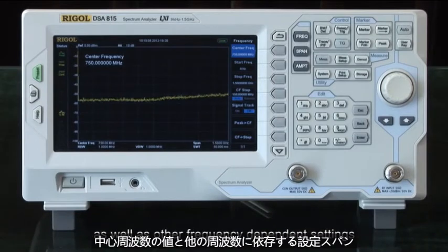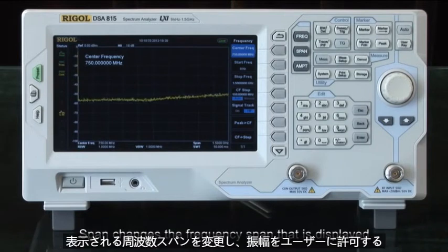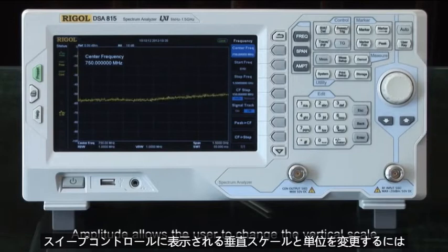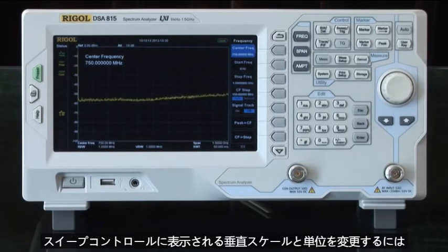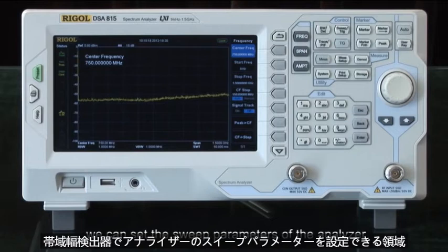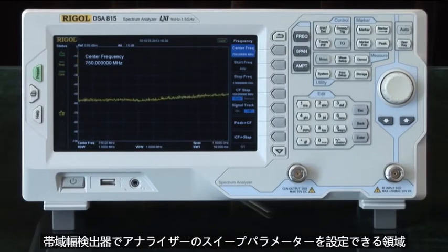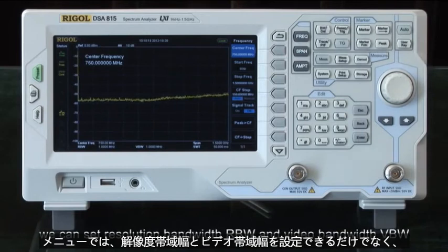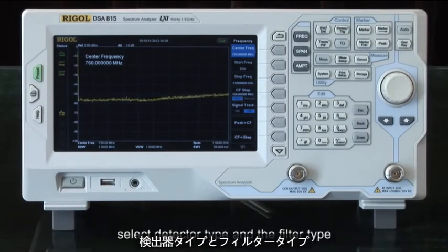Span changes the frequency span that is displayed, and amplitude allows the user to change the vertical scale and units being displayed. In the sweep control area we can set the sweep parameters of the analyzer. In the bandwidth detector menu we can set resolution bandwidth, video bandwidth, as well as select the detector type and the filter type.